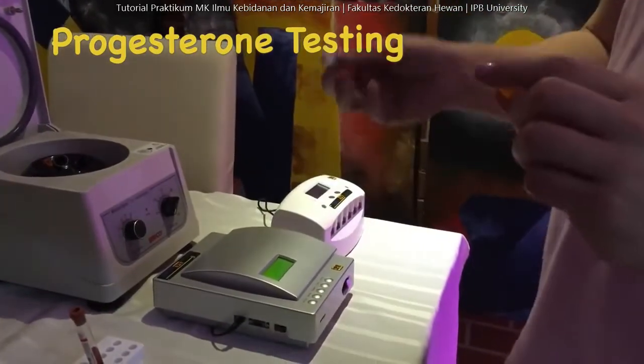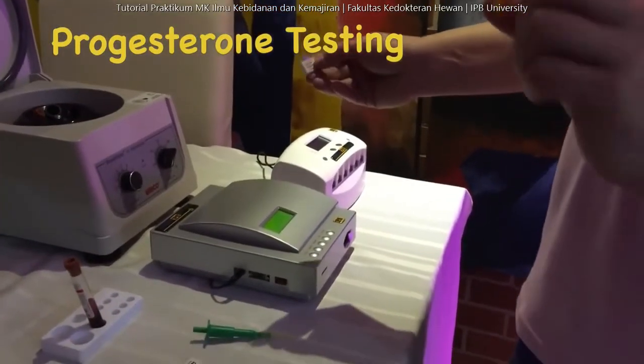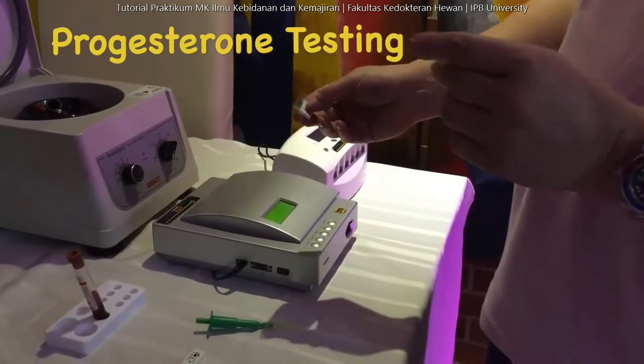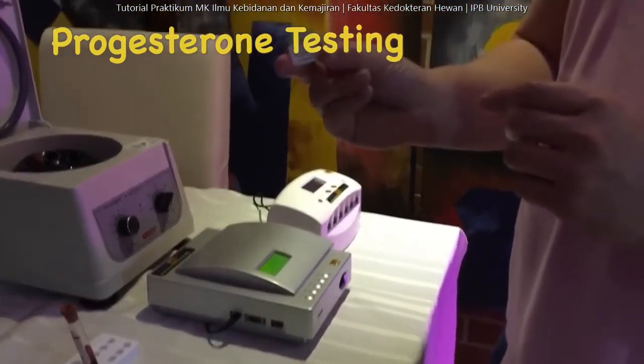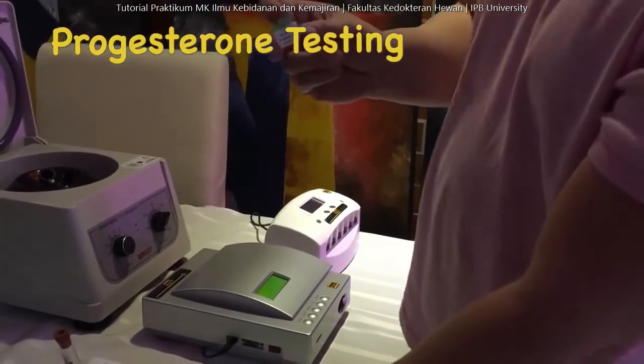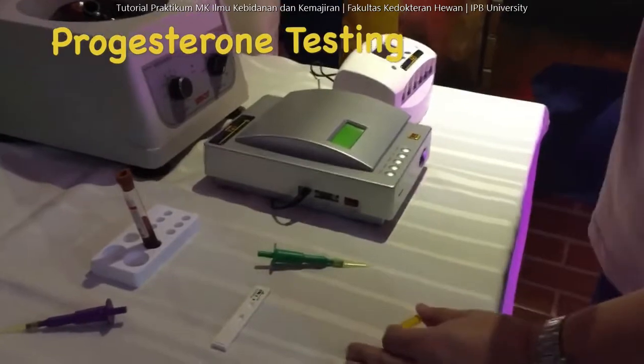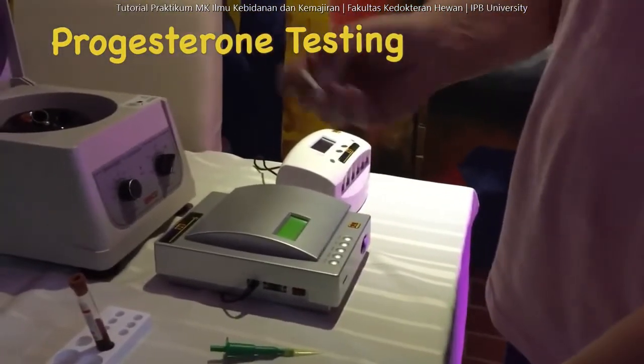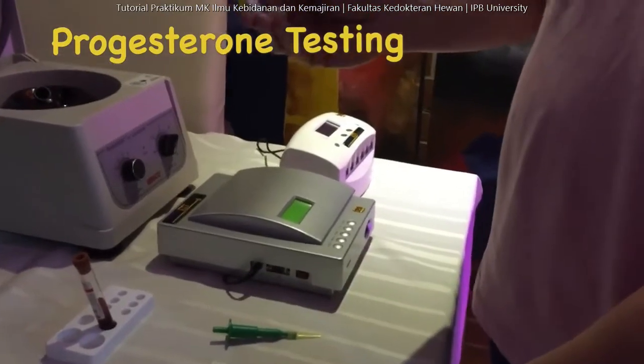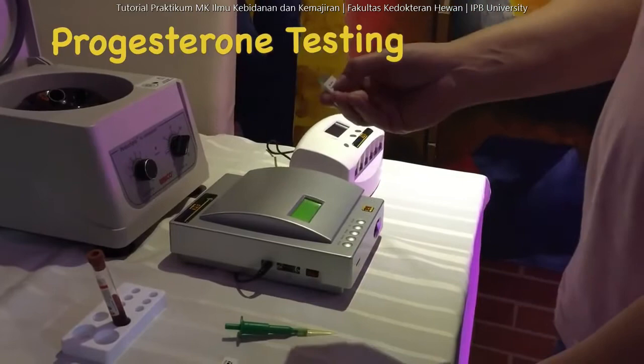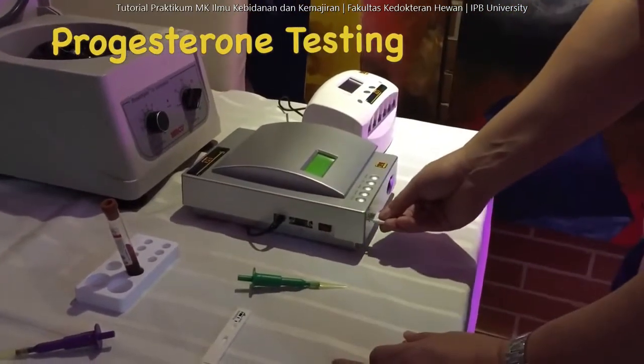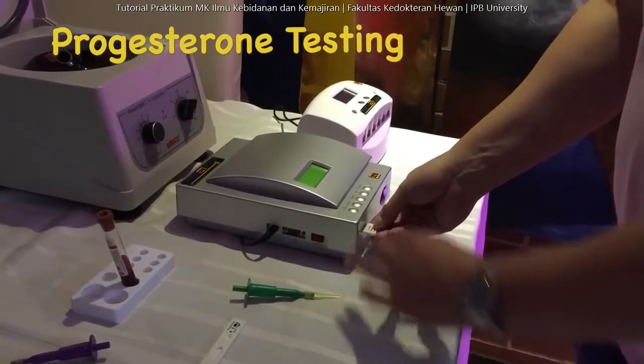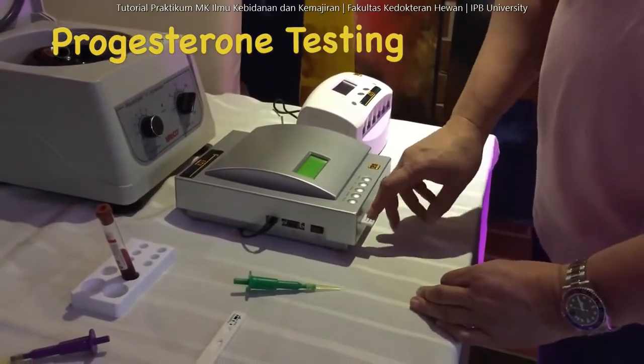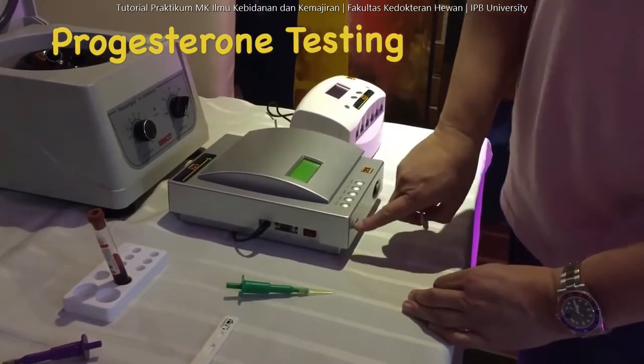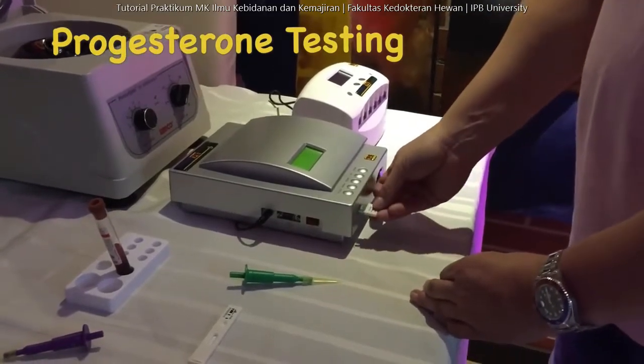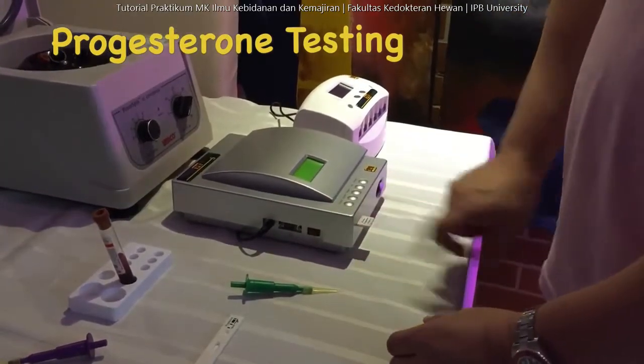Okay, the machine does not need any calibration or does not need any curves. The curves is right here in this microchip. It comes in boxes of 25 tests, and each box of 25 tests comes with one microchip. If it's the same lot number, you can use the same microchip if I send you 100 tests or 200 tests, but you want to make sure that you always have the same lot number with the test strips. Okay, so you put the microchip in here. Make sure you have the lot number facing up. Some people try to put this microchip the wrong way and you break the teeth inside the machine, and well, we would have to replace the inside part.